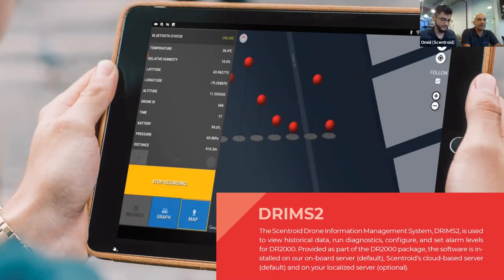Things like the PID, after 6,000 hours - something similar, 6,000 or 8,000, I'd have to look it up - comes to around 6 months of continuous use before it needs a new PID lamp. In a drone, these things will come up less because you're not running it 24 hours a day, you might run it like 10 hours a month. So the sensor will last the full 24 months until its shelf life expires, and the PID will last probably 10 years if you clean it every now and then.